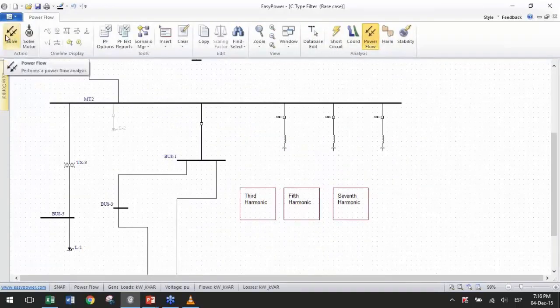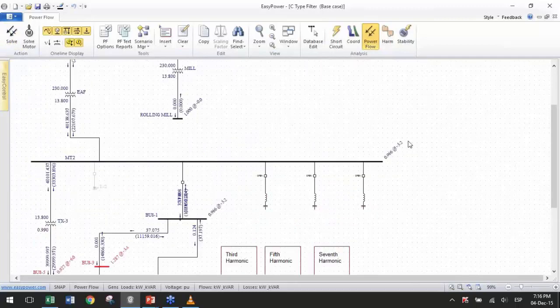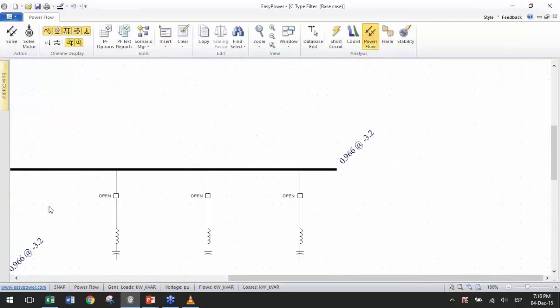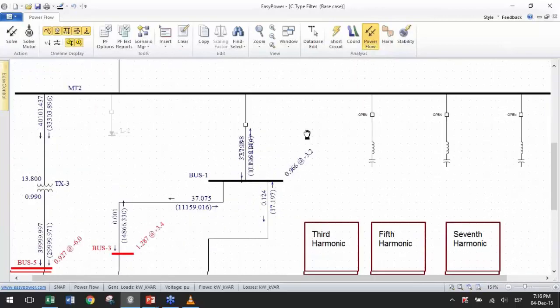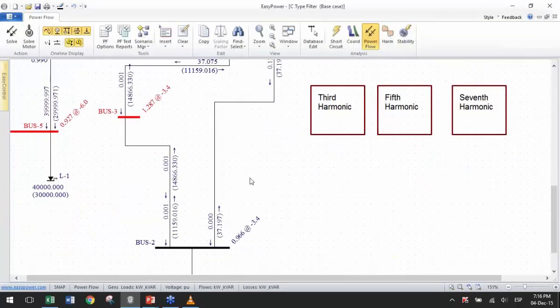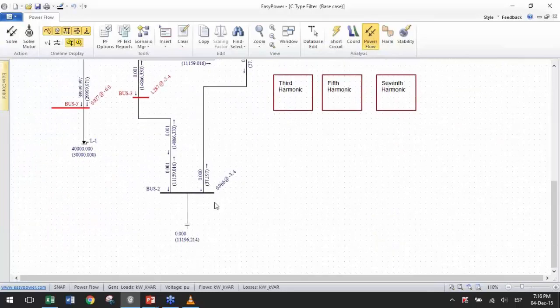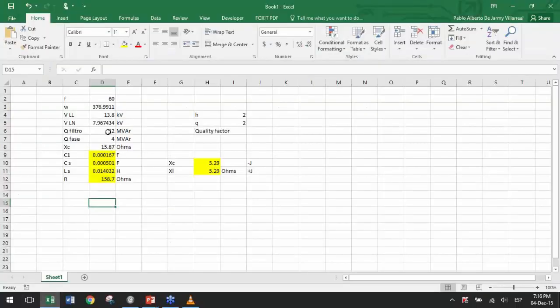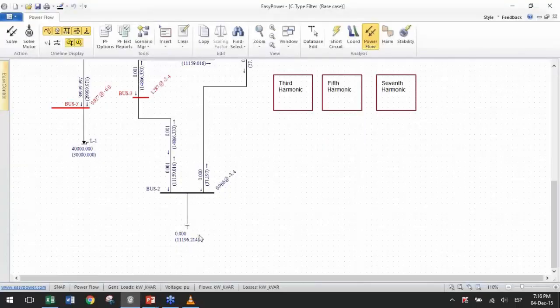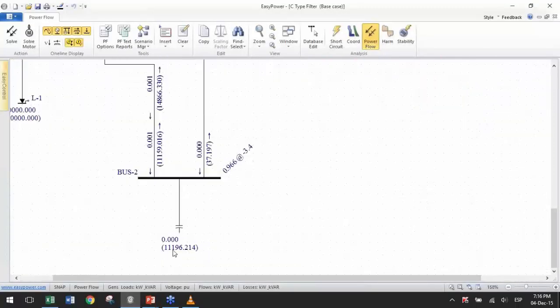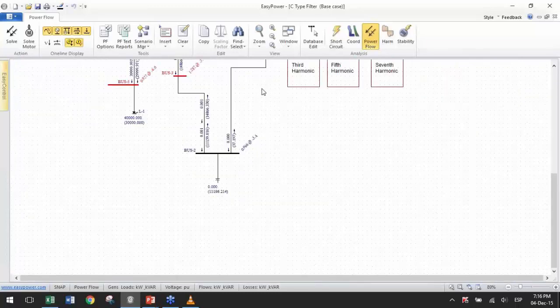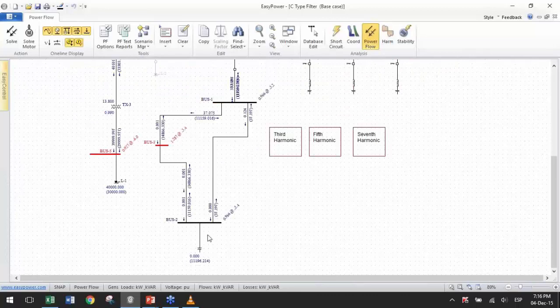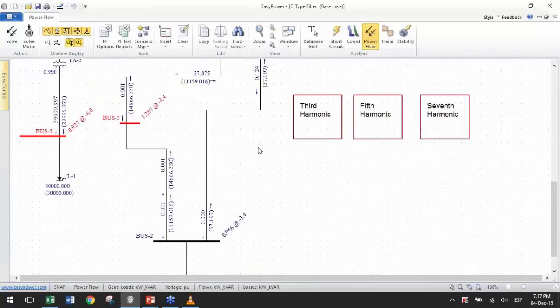When I make a power flow analysis, you may notice the voltage is a little low, doesn't matter. But the important thing is how the filter is working. Remember, this is a 12 MVAR filter, and it's producing 11.19 MVAR because the voltage is a little lower, which is fine, but it pretty much works exactly how I want, power-wise. Now, there are some very interesting things to notice.